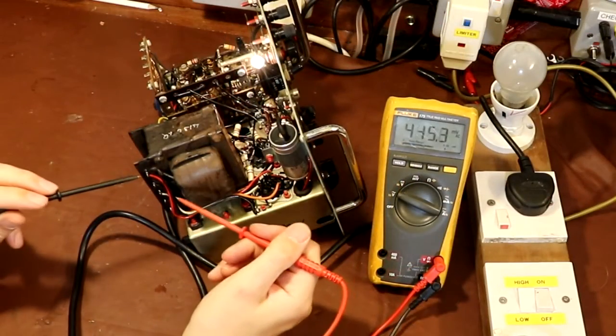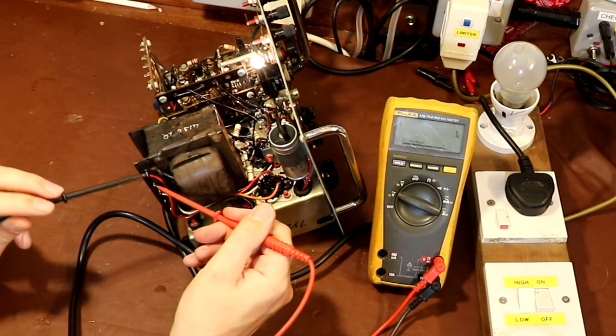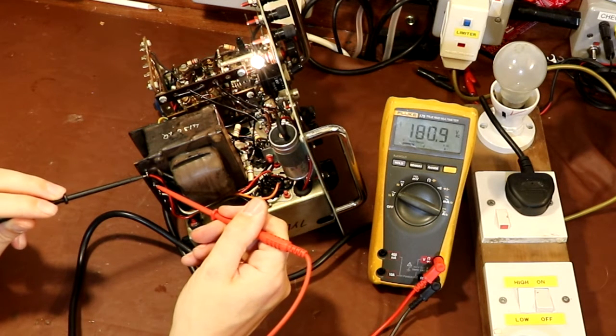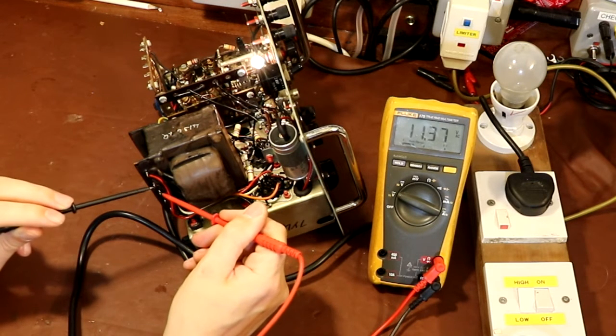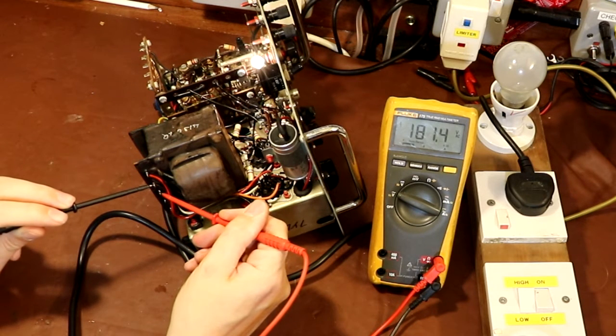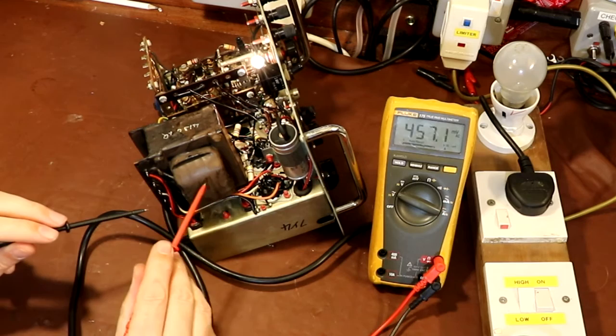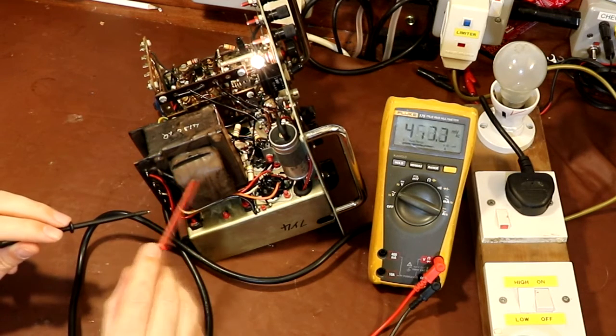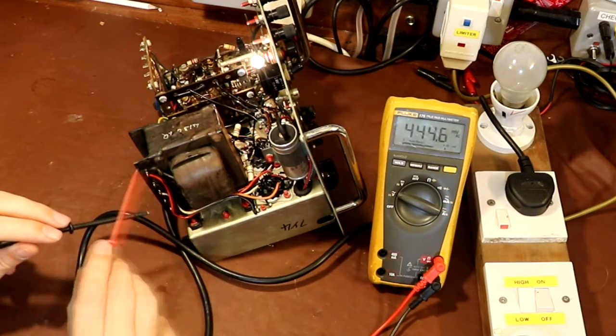So let me check our centre tap voltages. Let's check the first half of the centre tap - we've got 181 volts on the first half, and 181 volts on the second half. That means there's no shorted turns or anything like that, so the high HT, the high voltage output on this transformer, is good.